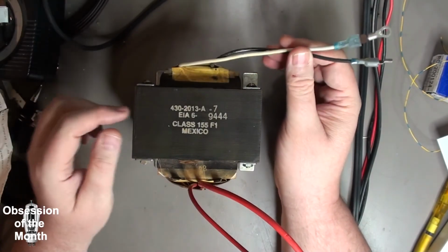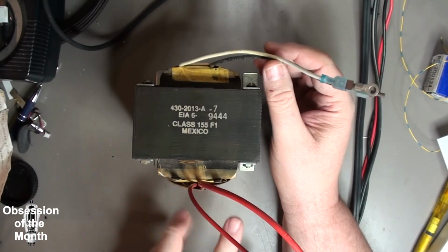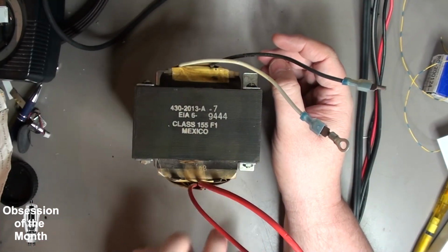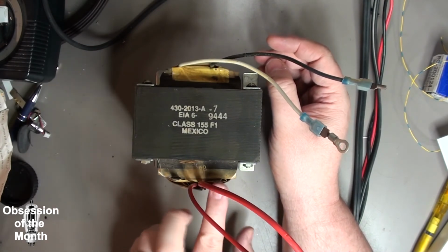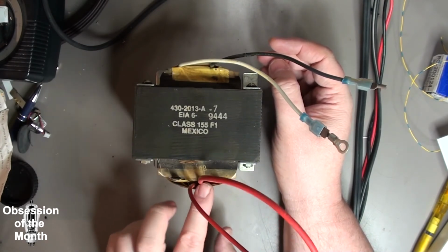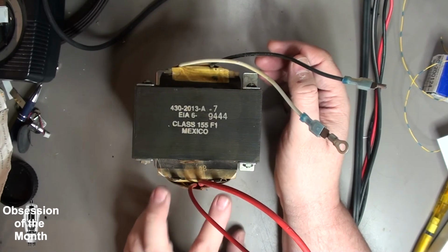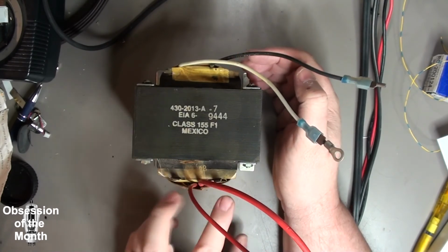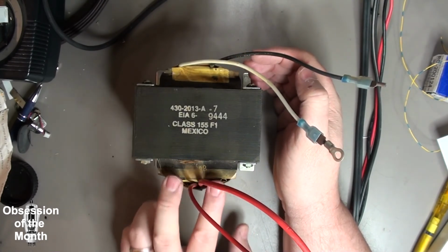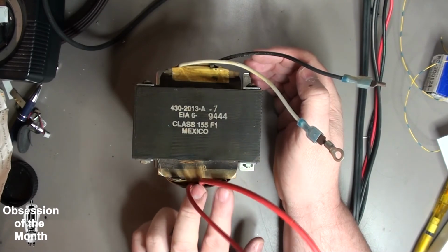So let's say you plug in 120 volts and don't get much amp draw. You bring it up to 120 volts, then measure the voltage across both terminals, and from one terminal to center tap to the other terminal to center tap. In this case, you get 62 volts on both sides and 31 volts to the center.